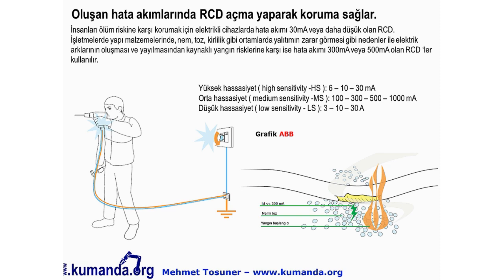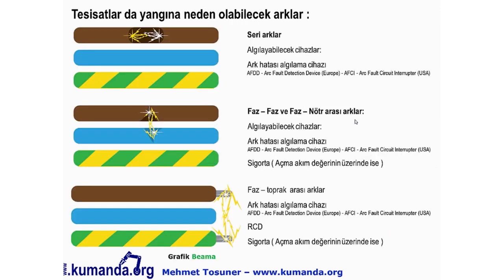30 mA insanların can güvenliğini sağlamak içindir. Eğer yangın riski varsa, 300 mA yangın riskine karşı koruyan RCD'dir. Tesisatlarda yangına neden olabilecek arklar; seri arklar (kablo kırılması, temas direnci, bağlantı gevşekliği) ve paralel arklar (faz-faz veya faz-nötr arası) şeklindedir. Seri arkları algılayabilecek cihazlar ark hatası algılama cihazlarıdır: Avrupa'da AFDD, Amerika'da AFCI olarak isimlendirilir.